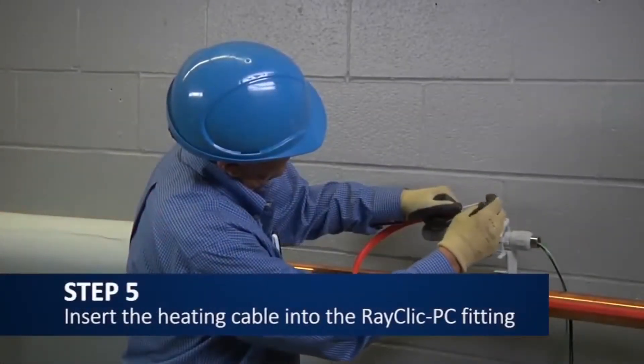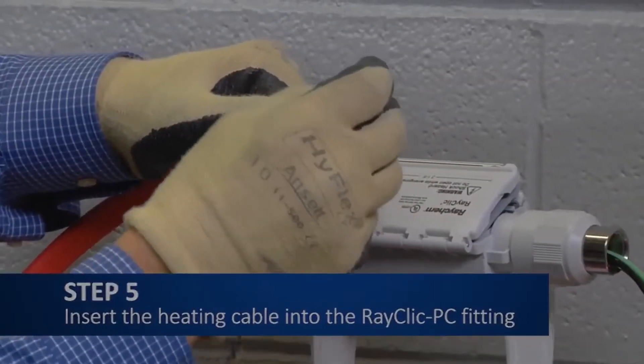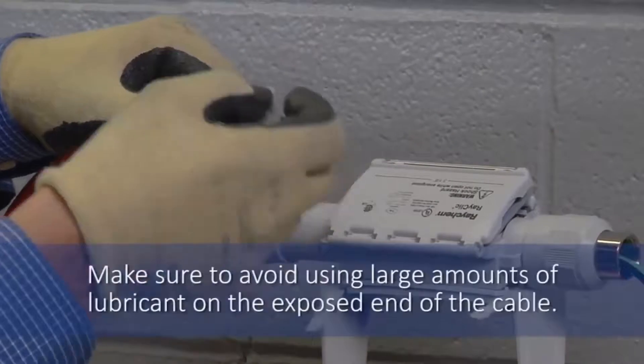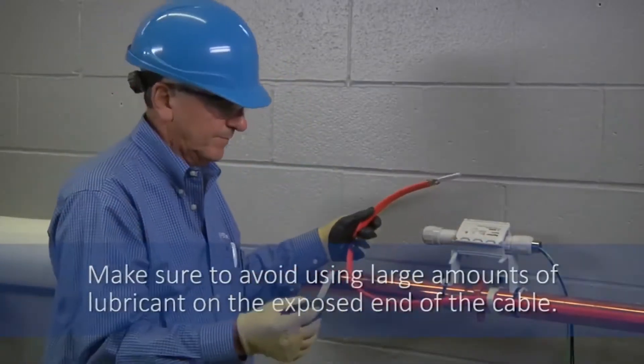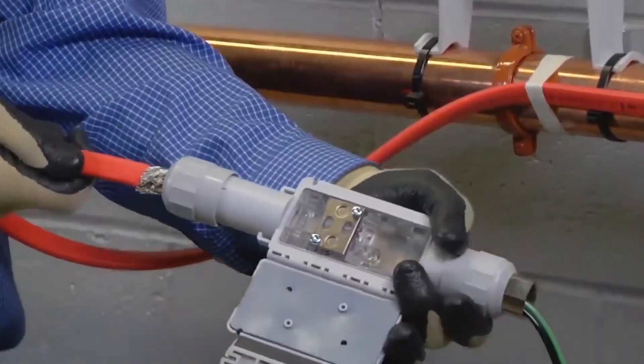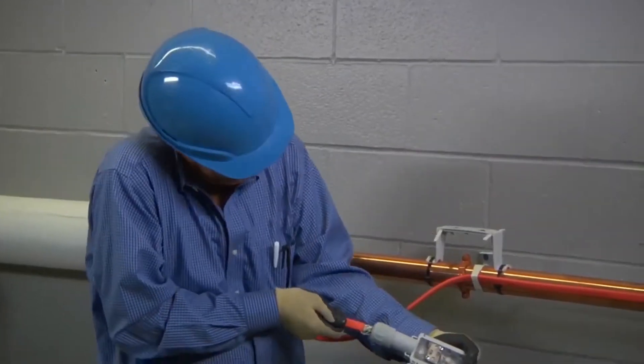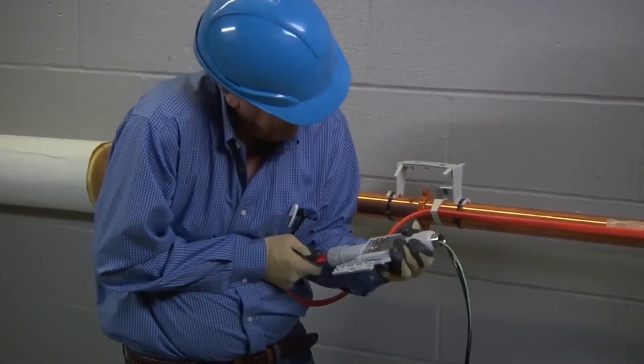Now, apply a small amount of supplied cable lubricant to the heating cable just in front of the ground braid clip. Make sure to avoid using large amounts of lubricant on the exposed end of the cable, and insert the prepared end of heating cable into the RayClick PC fitting by pushing the cable through the gland nut and rubber boot into the connector.